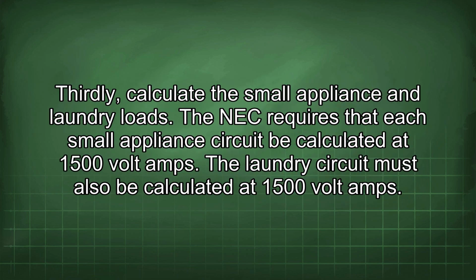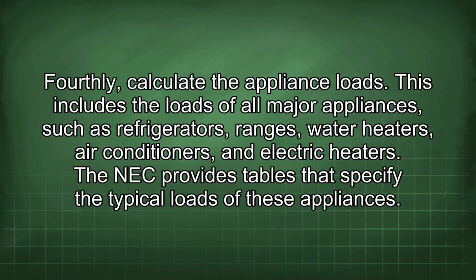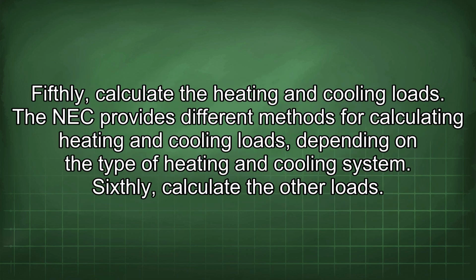commercial building. Thirdly, calculate the small appliance and laundry loads. The NEC requires that each small appliance circuit be calculated at 1500 volt-amperes. The laundry circuit must also be calculated at 1500 volt-amperes. Fourthly, calculate the appliance loads. This includes the loads of all major appliances such as refrigerators, ranges, water heaters, air conditioners, and electric heaters. The NEC provides tables that specify the typical loads of these appliances. Fifthly, calculate the heating and cooling loads. The NEC provides different methods for calculating heating and cooling loads depending on the type of heating and cooling system.